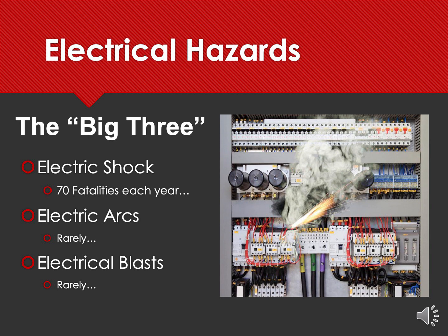One thing that we can take for sure is that industrial control panels almost always have electrical shock hazards. In fact, the data you can see on the slide here is that there are 70 fatalities, electrocutions, each year on industrial control panels on the job. Sometimes the small wires you see in these enclosures may lead one to believe there are no hazards there, and there almost always is an electrical shock hazard associated with industrial control panels.